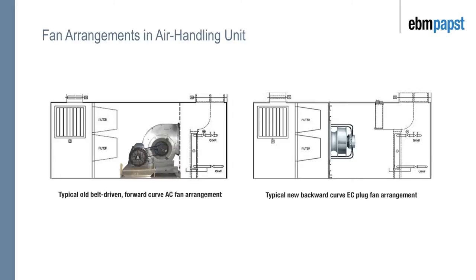Here's an example of a plug fan and how it's arranged, typically without housing. Here are some images showing the use of backward curved plug fans without housing and forward curved fans in an air handling unit. The layout of the fans is fundamentally different: the backward curve plug fan is positively pressurizing a plenum, whereas the forward curve fan is blowing air in the direction of a duct. The air intake on the two fans is also completely different.